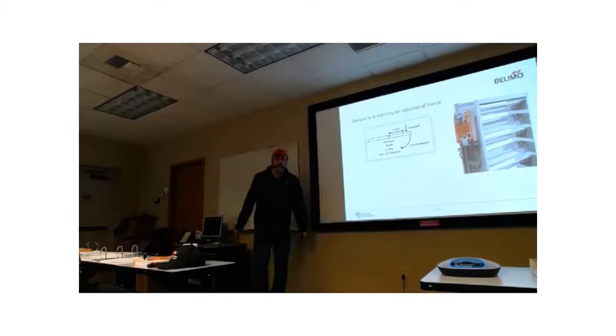Okay, got enough of that. So here's the basic deal we're going to go through for this next section. We're going to go through an example that shows you how to get the damper area in square feet — it has to be in square feet — and we're going to come up with this torque loading factor in inch-pounds per square foot.